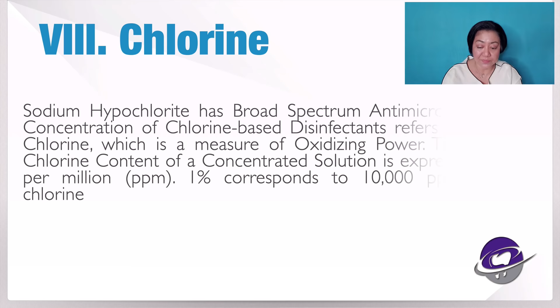Next is chlorine. The most popular is sodium hypochlorite, which is very good for cleaning the water lines. When you use chlorine, dilution and contact time is 1:10, or a 10% solution, with 10 to 15 minutes exposure. For iodines, the dilution and contact time is 1% with 10 minutes exposure, while for peroxide, meaning hydrogen peroxide like Hyperox, the contact time is 20 minutes. Only 5 to 10 minutes is needed for a 1% dilution of Virkon.